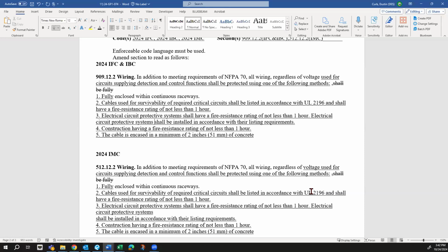The ratings and stuff follow most sprinklered buildings. If you're looking at a 1 hour rating, that's for running through a sprinklered building where it's not exposed, above a hard lid and a sprinklered ceiling, for detection—because at the top it says detection and control circuits shall be protected. It's not specifically the ventilation circuits required as part of 909, which has specific 2 hour requirements all the way back. Same with the fire panel or graphic panel controlling these—it's all 2 hour protected, no variation. This is stuff on the outlier that seems to be encompassed.